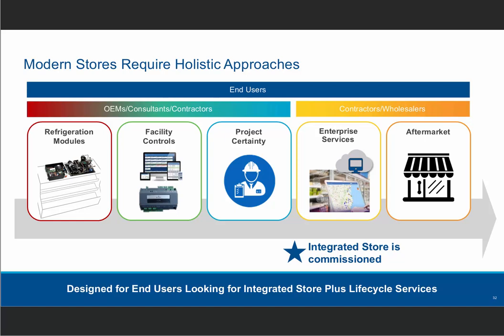usually supplied by OEM, that's going to put together all the components, all the technology. But then when you think about smart and integrating that store, you have the second piece, which is the facility controls, usually integrating all those equipments in the floor of the store. Also, every time a new store is being set up, there is the concern about the project management piece of that store, or the certainty around setting up that store on time and in full. And when I say in full, it means making sure that every piece of equipment is going to be integrated properly and is going to be functional by the time that the store is commissioned. That is the third piece.